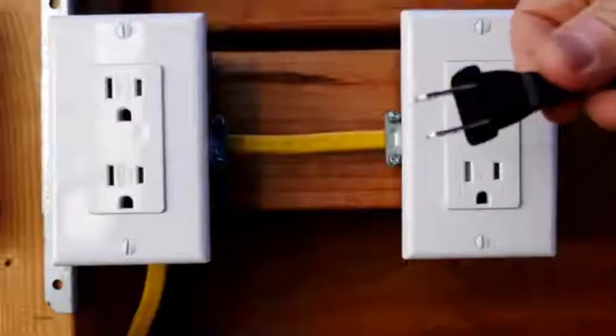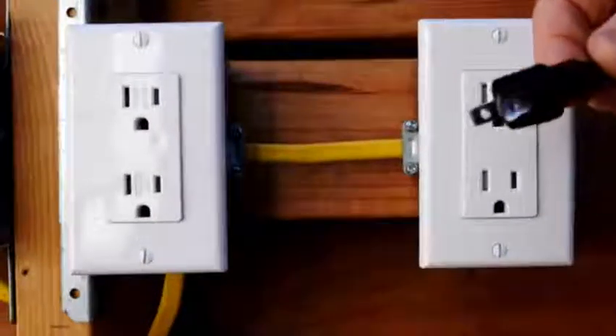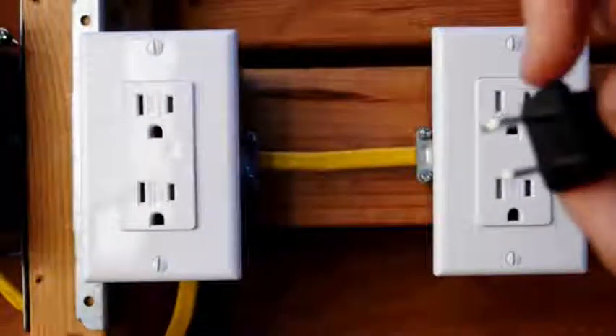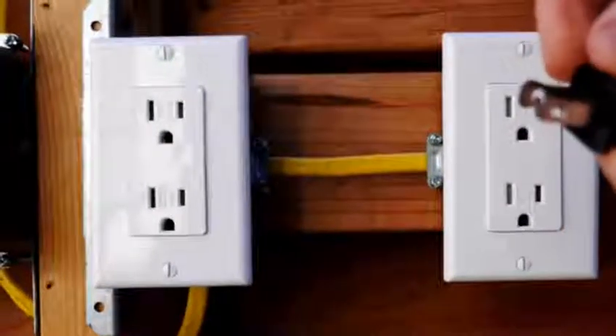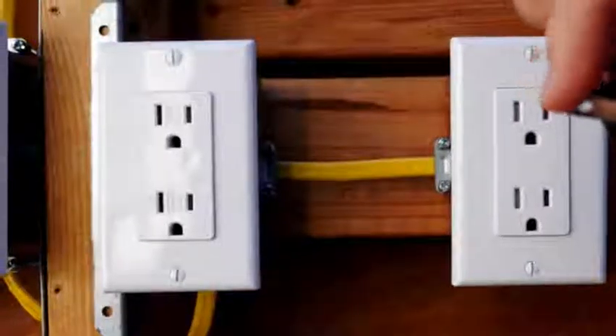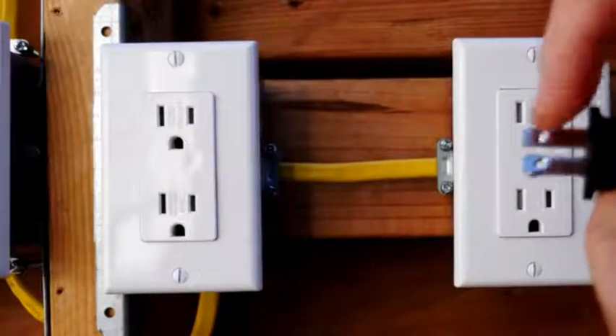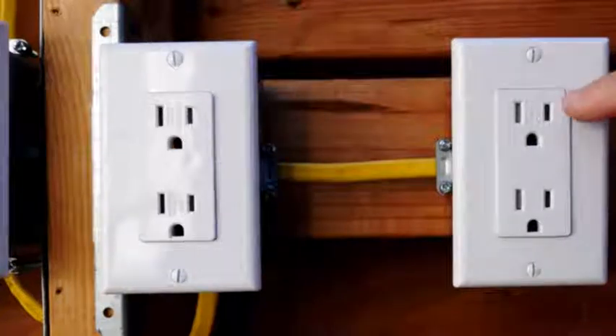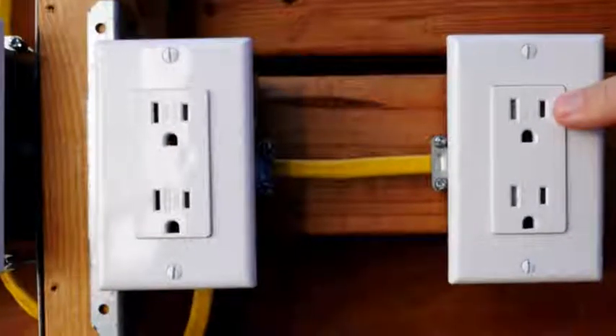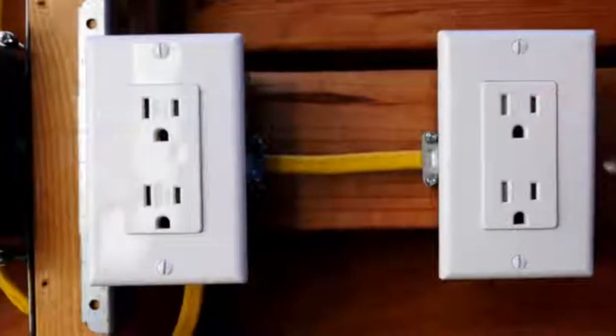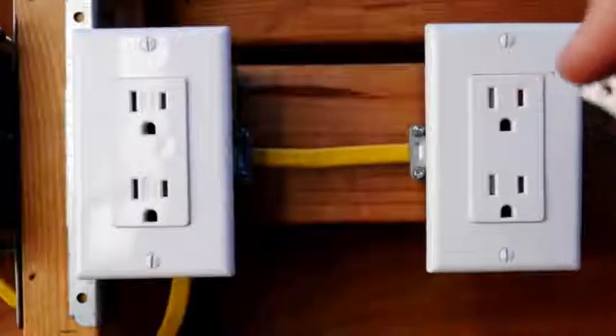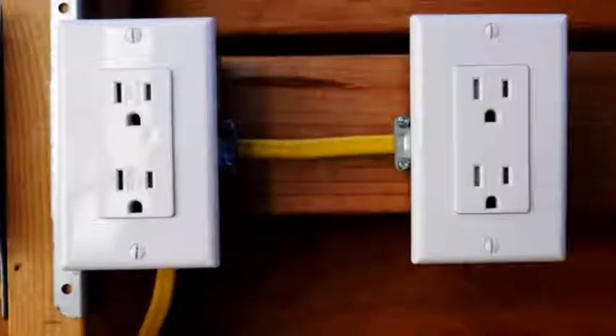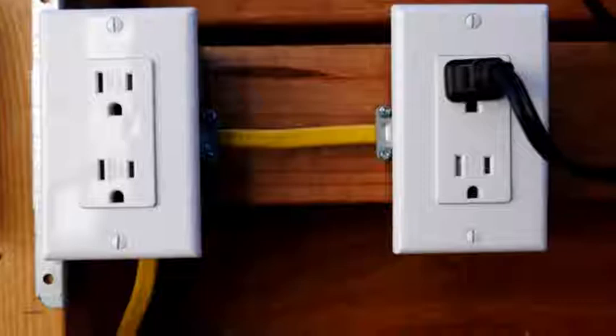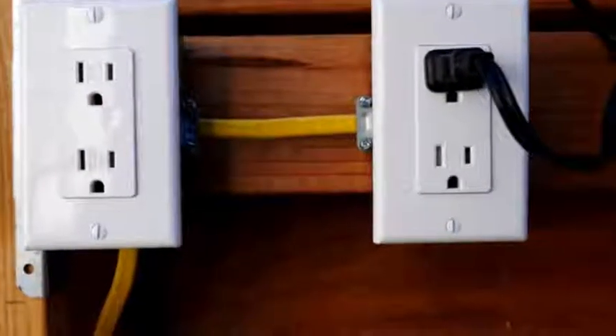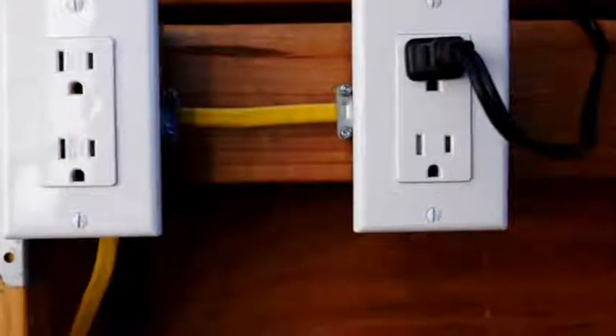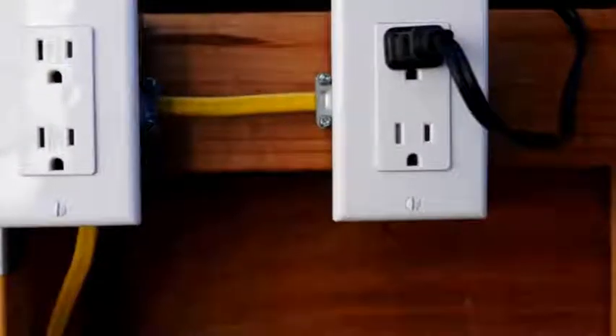Here is a polarized plug, just a common household polarized plug. This prong is wider than this prong. This smaller prong is designed to go into the hot slot, that's the smaller slot. The larger prong is designed to go into the neutral slot. Since this receptacle has reversed polarity, it's going to give us a shock hazard, and your appliances may not last as long.